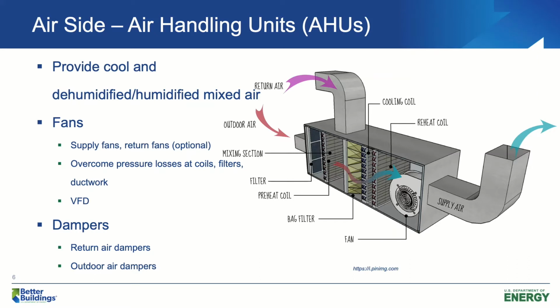Sometimes we also have some return fans, but return fans are optional. If we do have return fans, we can select smaller motors for the supply fans. We would like to recommend having VFDs on the supply fans. This way we can provide just the right amount of cool air to our spaces, and we can avoid overcooling spaces. If we provide too much cool air to spaces, we might need to reheat the air temperature up again. That's a waste of energy.